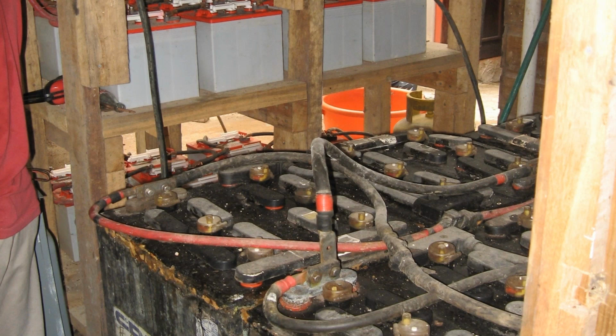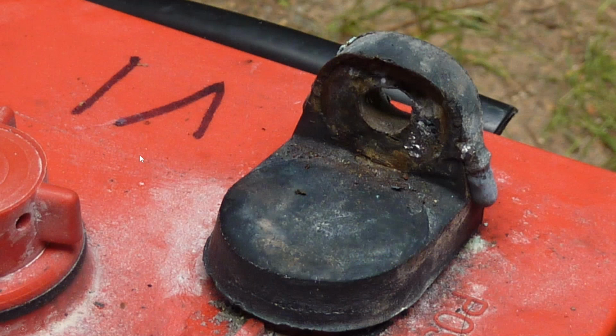Even with the Series 5000 batteries, if you get a voltage measurement on the top of the battery without connecting it to a piece of metal, you've got problems. You definitely have issues. For example, this battery bank here: not only have they mixed all different types of batteries, but if you took a volt measurement, connecting your positive lead to here and your negative lead right to here, we would get voltage. And that voltage is detrimental to the system.